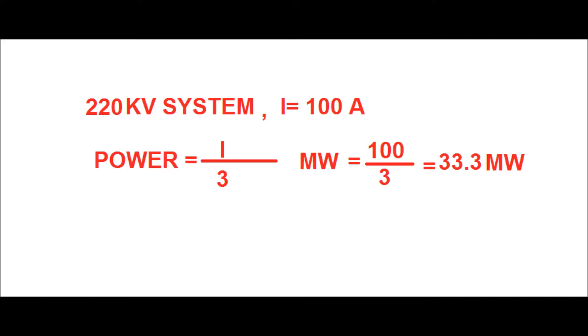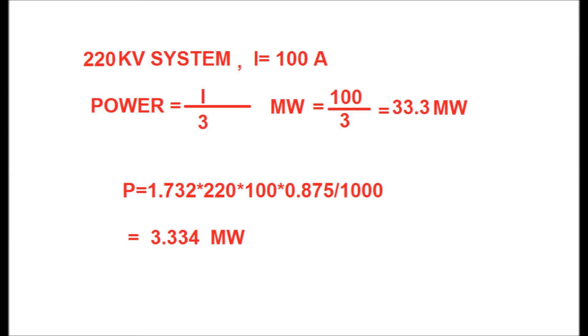For a 220 kV voltage system, if current I = 100 amperes, to get the value of power in megawatts just divide the current by a factor of 3, giving 100 divided by 3 equal to 33.3 megawatts. Using the formula: P = 1.732 × 220 × 100 × 0.875 divided by 1000, with power factor 0.875, you get P = 33.34 megawatts.